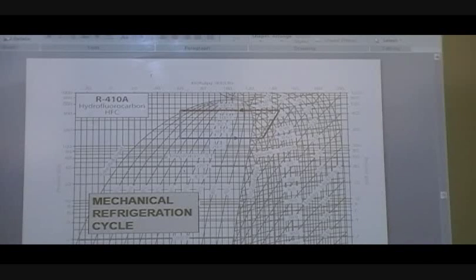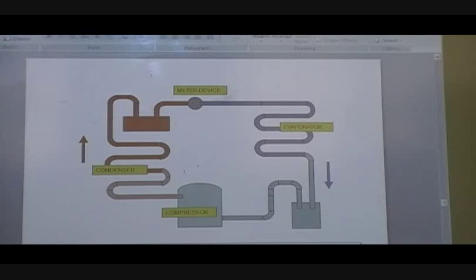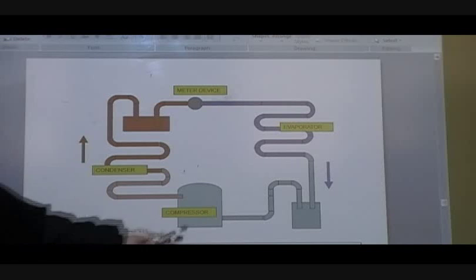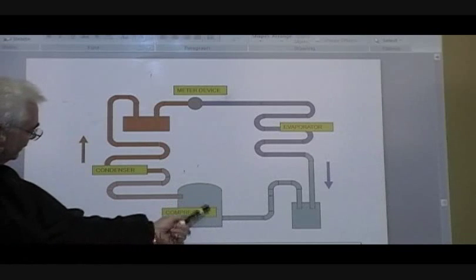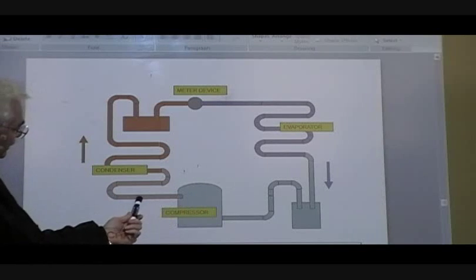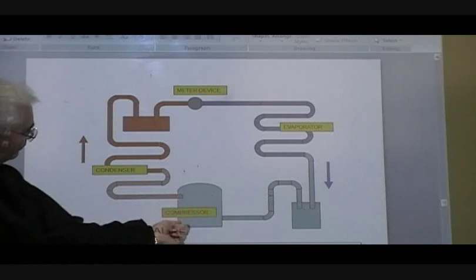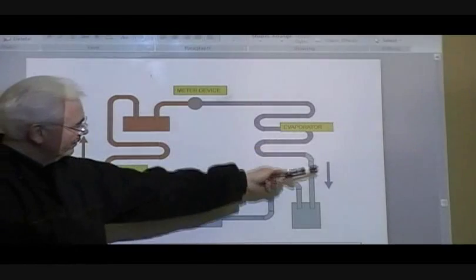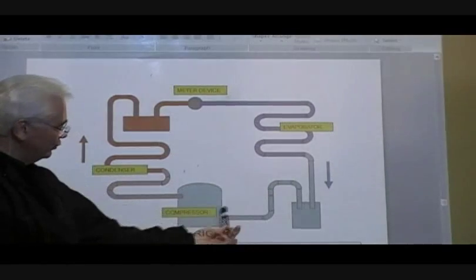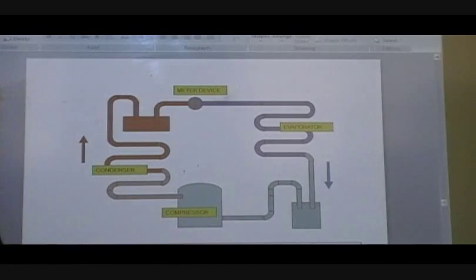All right, we'll move on to the next chart. The thing about the pressure-enthalpy diagram, it's a graphical representation of what's happening in that refrigeration system. You've got your compressor, you've got your vapor coming in, and it pumps the vapor up to a high pressure, you've got your vapor leaving, and remember, the compressor is a vapor pump. If for some reason you have a malfunction and you get liquid back to that compressor, that's bad news.